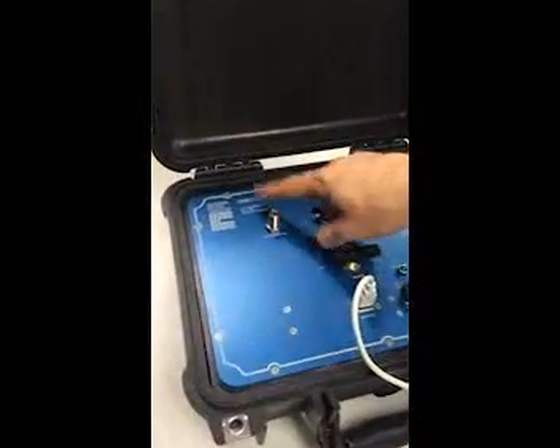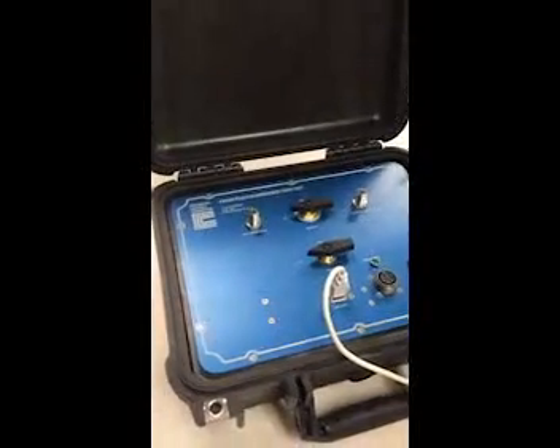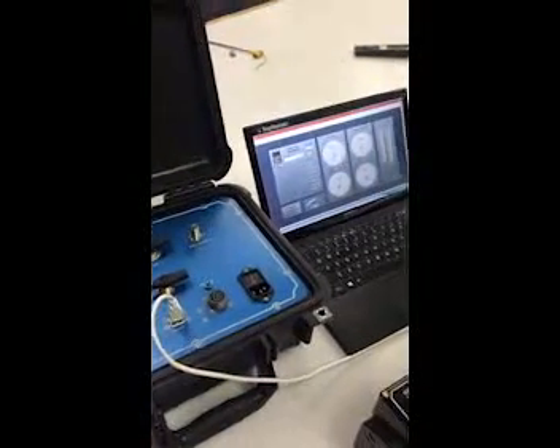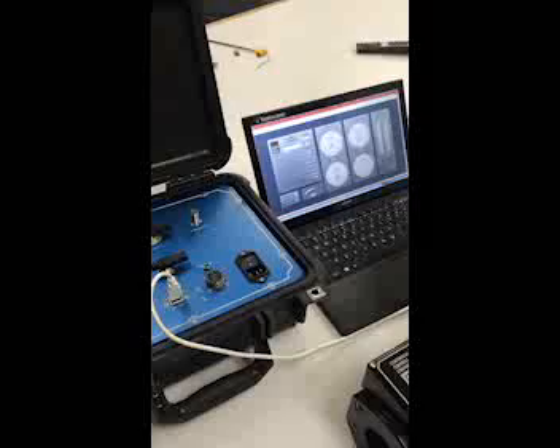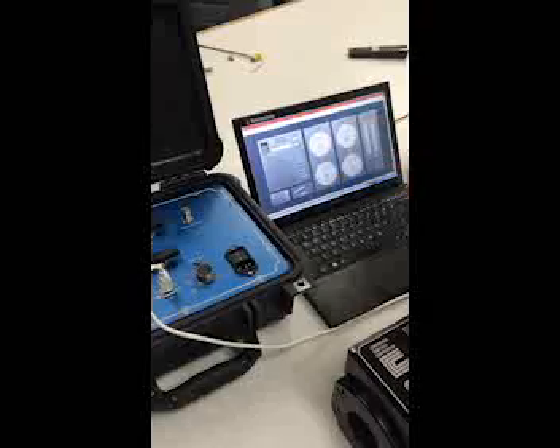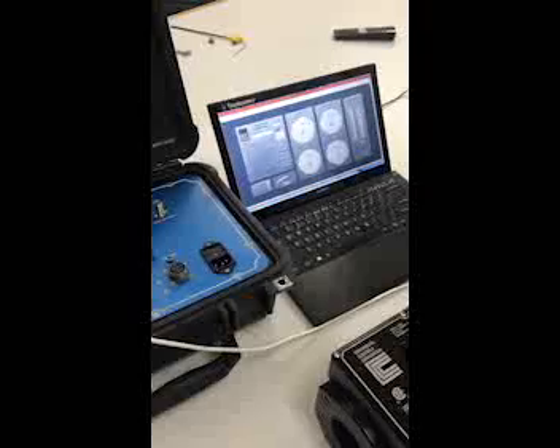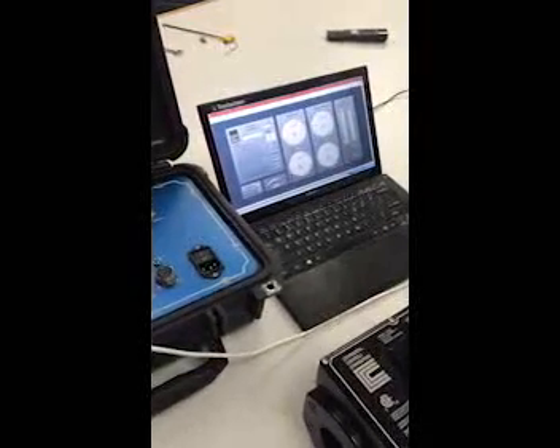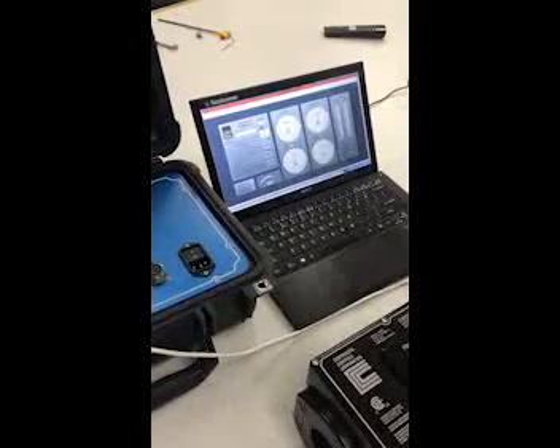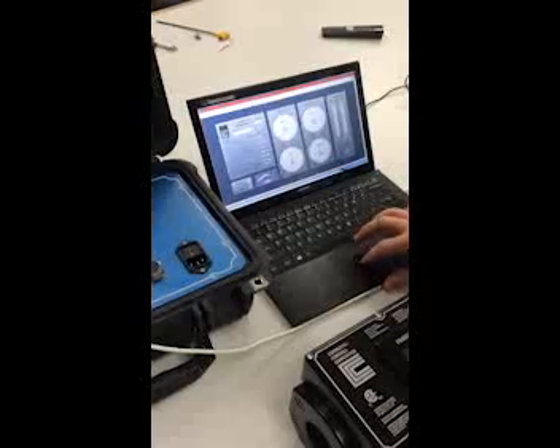The test set serial number is found on the FM50 test set. So your serial number is there. For this demo, it's serial number 100. We're going to type in 100 there. Then customer name and notes. Again, any notes about this application that you think are relevant. At the very end of the procedure, we're going to be able to print up a report. So if you want any notes or anything custom to show up on that report, that's a good spot to fill it in. On your COM port, there's a drop-down box, and you'll select the appropriate COM port. Once you plug in, you'll see where those go. A more detailed explanation of COM ports and troubleshooting can be found in the flyer that's part of your FM50 test set. So we connect to our COM port. Number 2, it says press run in the upper left arrow.